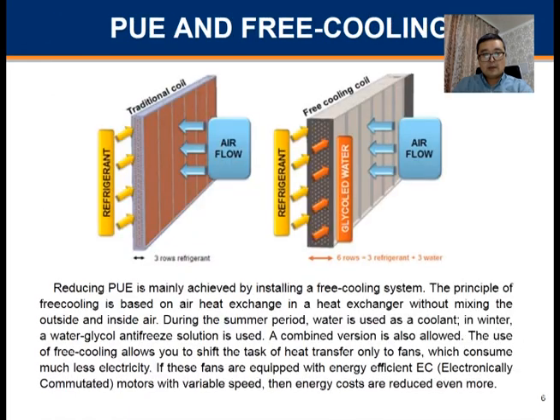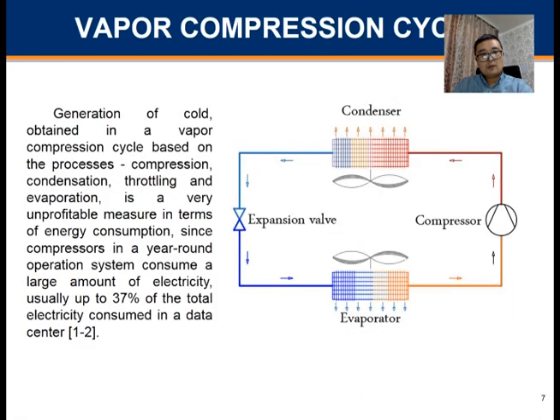Reducing PUE is mainly achieved by installing a free cooling system. The principle of free cooling is based on heat exchange in a heat exchanger without mixing the outside and inside air. Generation of cold is obtained in a vapor compression cycle based on the processes of compression, condensation, throttling, and evaporation.